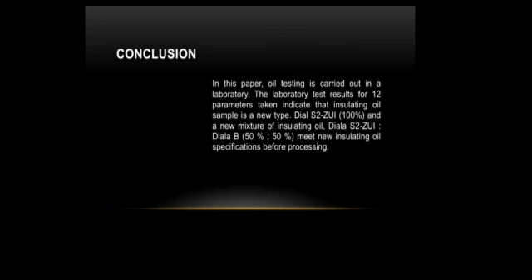Conclusion. In this paper, oil testing is carried out in a laboratory. The laboratory test results for the 12 parameters taken indicated that the insulating oil sample of the new type Diala S2 ZU-I 100% and the new mixture of insulating oil Diala S2 ZU-I and Diala B, 50% to 50%, meet the new insulating oil specification before processing.